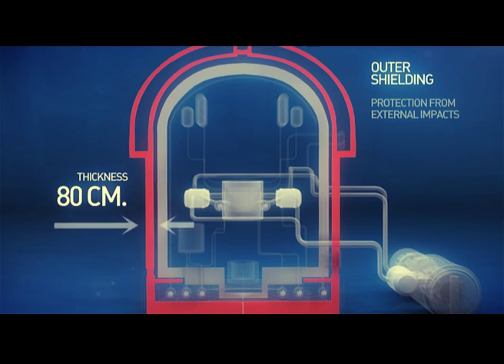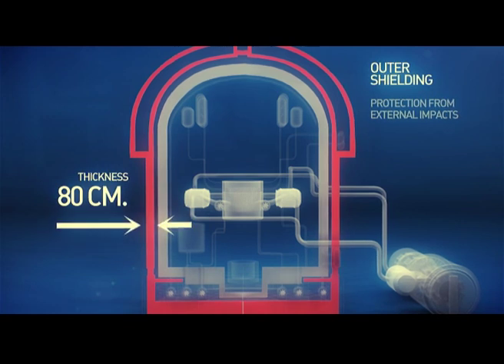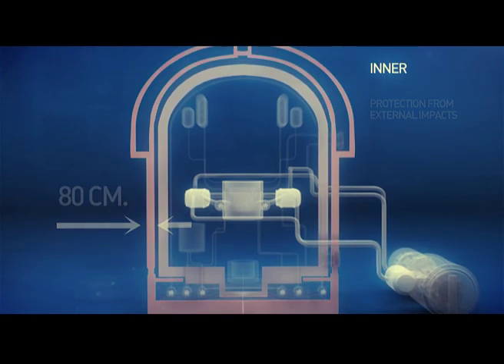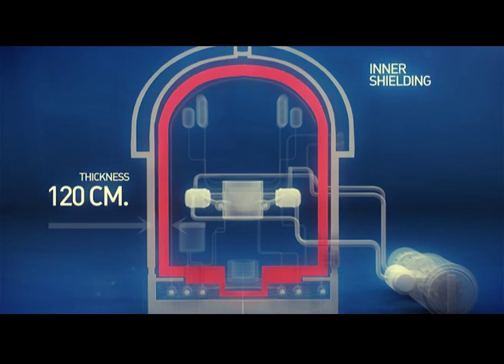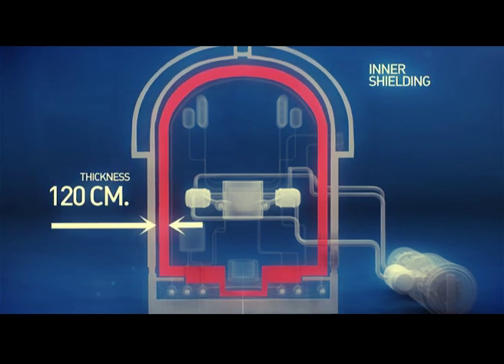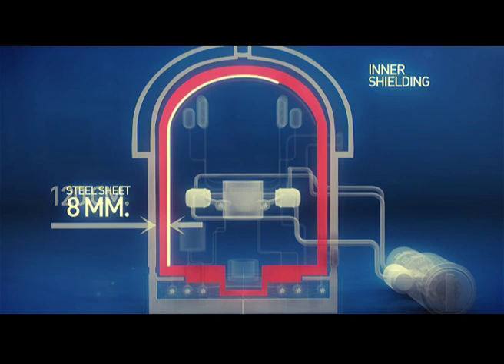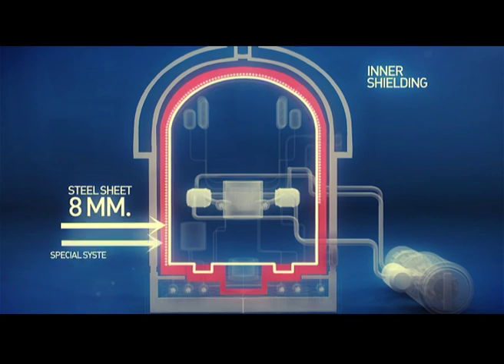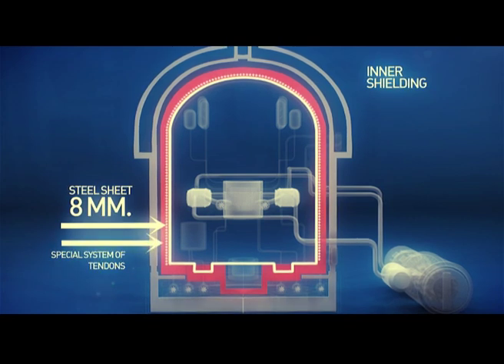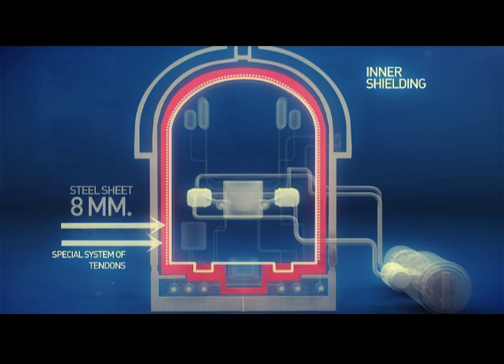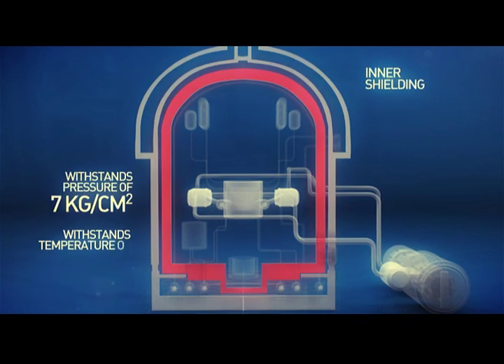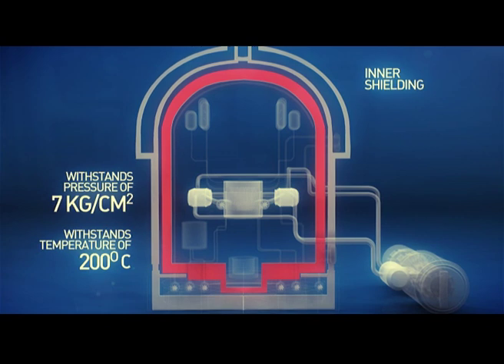The inner shielding is a concrete wall of 1 meter 20 centimeters in thickness. From inside, it is lined with steel sheet of 8 millimeters in thickness and is reinforced with special systems of wires strained inside the shielding. In essence, it is a contracting steel cocoon, which increases strength of concrete compression by nearly three times. The inner shielding can withstand a pressure of 7 kilogram per square centimeter and a temperature of up to 200 degrees Celsius.